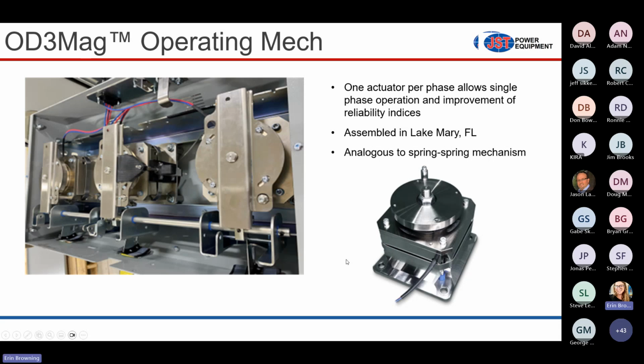Again, the actuator itself is relatively small, but heavy. If you've been to Lake Mary, you've probably picked one of these up. This is a single coil magnetic actuator. This is the same kind of actuator that has been used in line reclosers for the last 25 or 30 years even. It's a single coil. Think of an inductive shaped donut, which generates a magnetic field depending on the voltage that's applied to it, either upward or downward. I'll get into the details of that, but it's compared to an ABB or a Siemens magnetic actuator for their outdoor breaker.